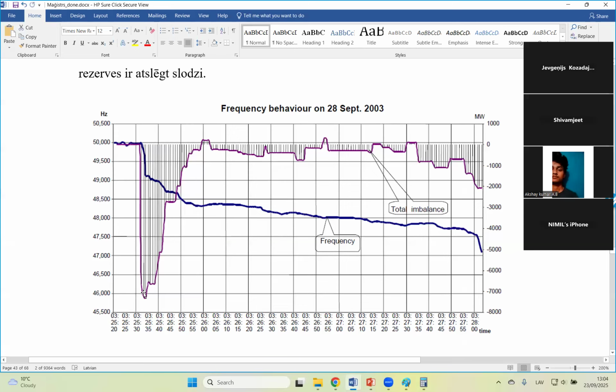Here we go, I think here you see 3 AM, 25 minutes. Here you see 25 minutes, 30 seconds. And the imbalance is 0 at 26 minutes past 3. So it took 30 seconds to restore the balance, to bring the system back to balance. So, very good. But what we see with frequency is that the frequency dropped to a value of 48, I'd say 0.3 hertz.